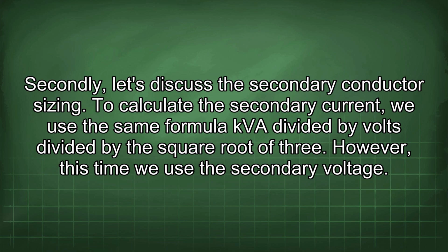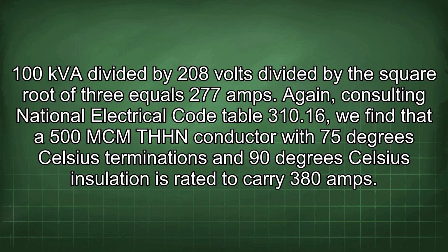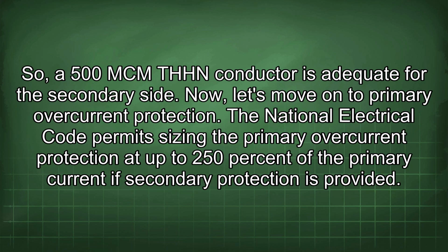Secondly, let's discuss the secondary conductor sizing. To calculate the secondary current, we use the same formula, kVA divided by volts divided by the square root of 3. However, this time we use the secondary voltage. 100 kVA divided by 208 volts divided by the square root of 3 equals 277 amps. Again, consulting National Electrical Code Table 310.16, we find that a 500 mcm THHN conductor with 75 degrees Celsius terminations and 90 degrees Celsius insulation is rated to carry 380 amps. So a 500 mcm THHN conductor is adequate for the secondary side.